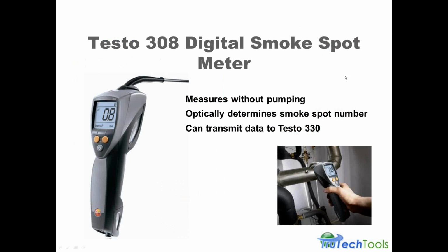But Testo has developed one that actually measures without pumping, uses an optical sensor to determine the smoke number. It can transmit or beam the data to a Testo 330, and it also has the ability to measure in tenths of the smoke spot number, so higher resolution on the display here.